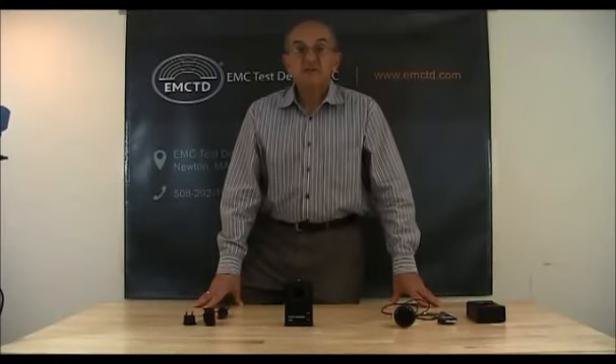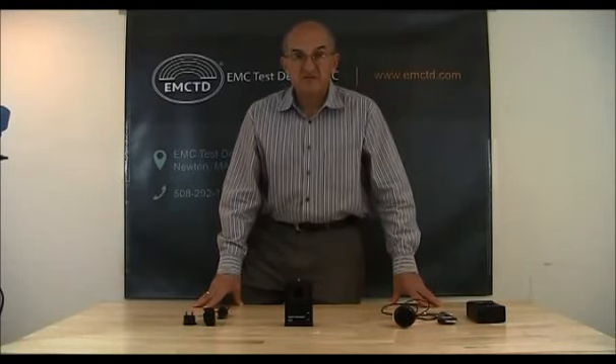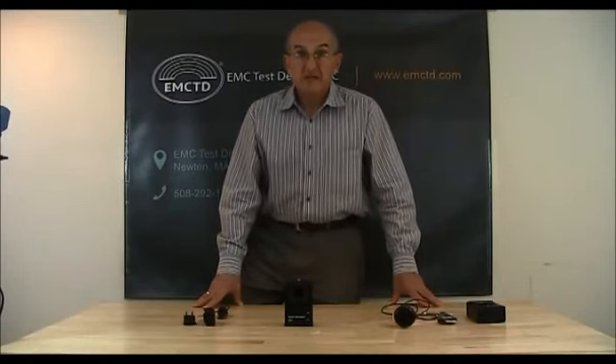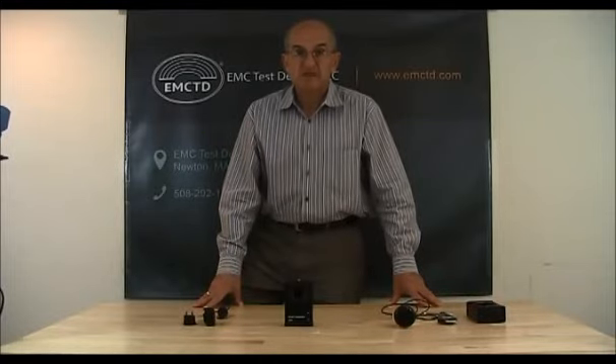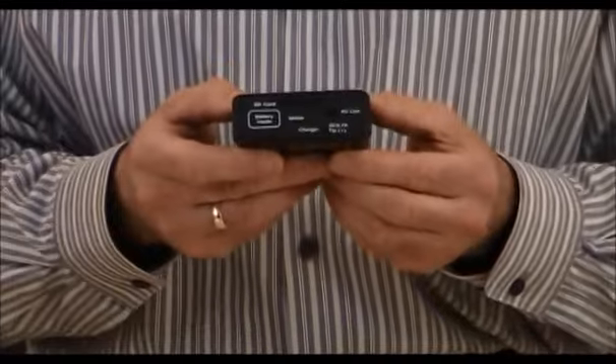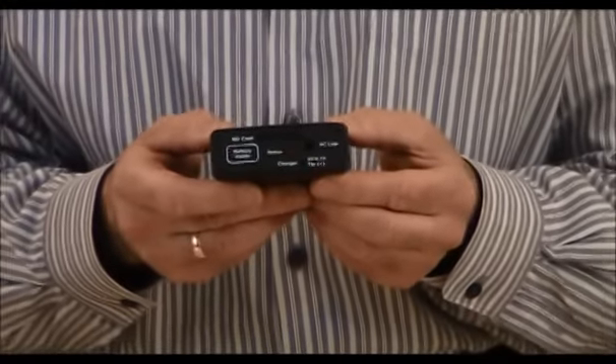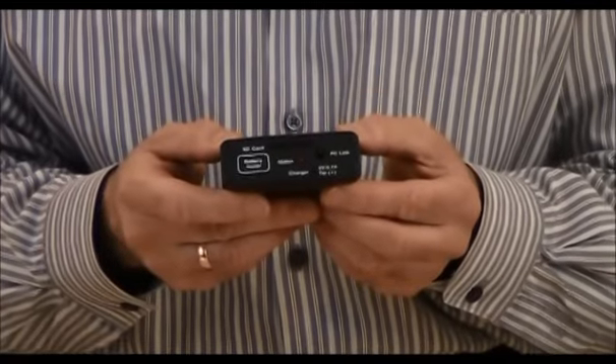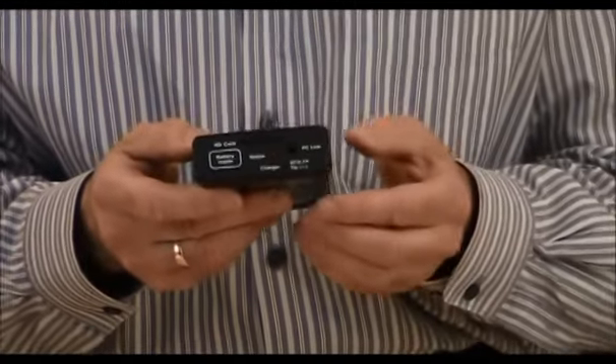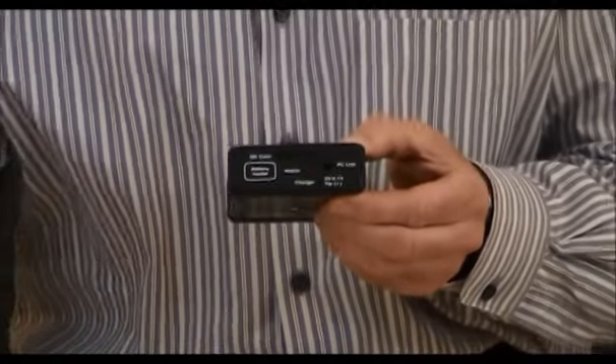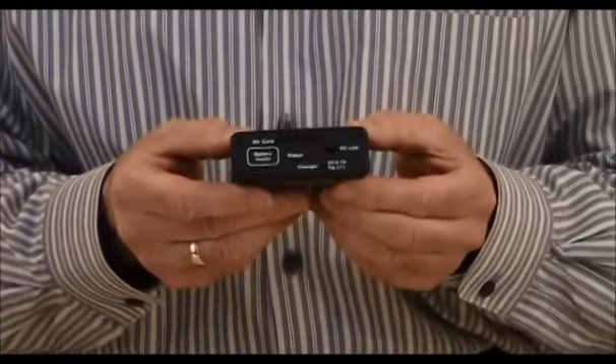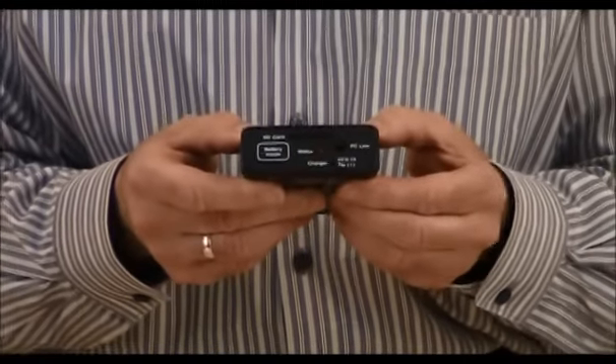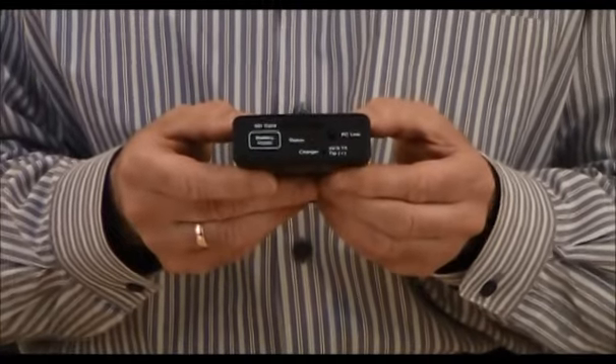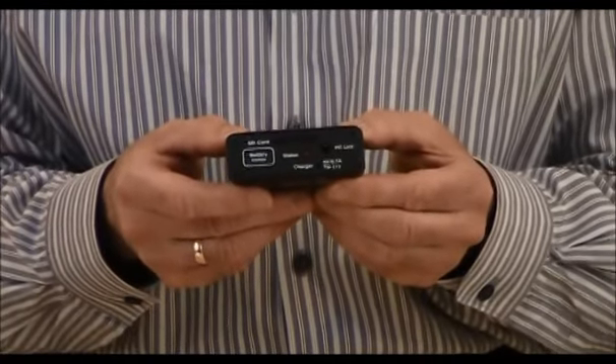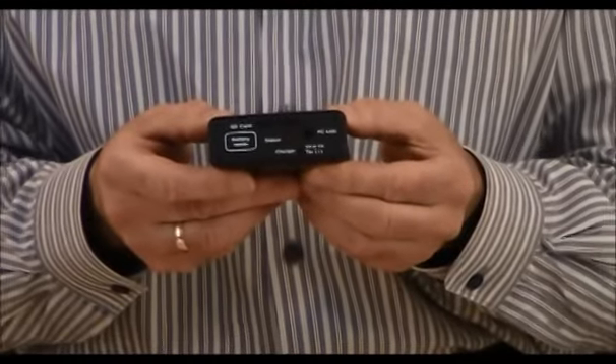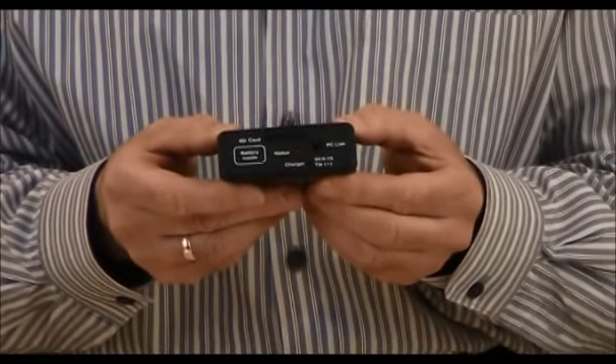There is also a LED that indicates the status of the charging. One set of rechargeable batteries will operate between 25 to 55 hours of continuous use, and standby time of this meter is about 1000 hours. Because this unit can take both rechargeable and alkaline batteries, it is very important to ensure safety and compatibility of these batteries and charger. So if you try to charge alkaline batteries it will not charge them, instead this LED will blink with duty cycle 50%, indicating that something is wrong. It also will not charge worn, low quality or defective rechargeable batteries.